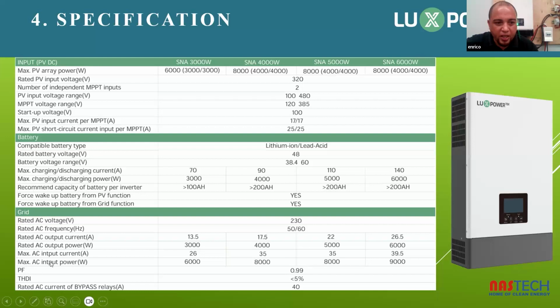The maximum AC input is also 8 kilowatt. So the voltage coming in from your grid can go up to 8 kilowatt. The solar panels that you have on the roof coming in per MPPT is 4 kilowatt each. In total that can be up to between 6 and 8 kilowatts on the roof. And then of course your battery that has a range of 38 to 60 volts.